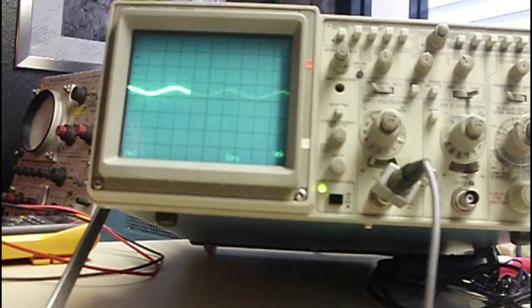There we go. Once it settles in, we're getting 2 millivolts peak to peak ripple on that, so we're okay there. Alright, now last but certainly not least, I'm having to move my ground clip, is the 585 volts. We'll have to turn down the gain a little bit. We're at 10 millivolts. So again, there's a little bit of low voltage noise ripple going on there, but it is not bad. And you can see we're getting 30 millivolts of ripple or so. We're in perfectly good regulation on all these. After 60 years, those caps are still working perfectly, which is amazing.